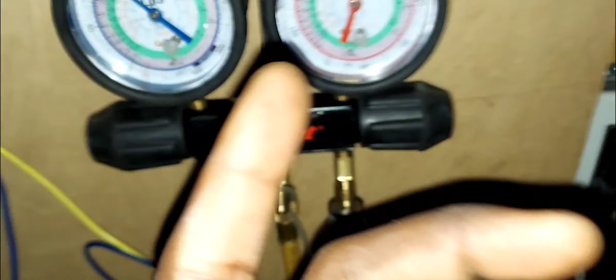Just so you know, the same way you have an automatic resettable low pressure switch, high pressure switches come that way too. This particular one is a manual reset. So if you have one with high pressure ranges listed on it, that's a high pressure switch, and it'll look similar to this.